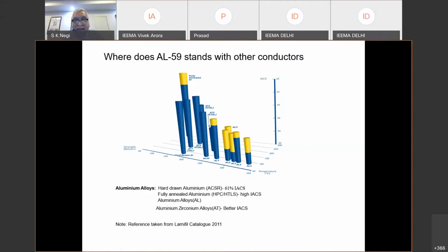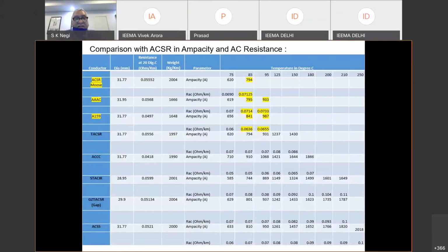So from this we see that AL59 conductor can stand up to 95 degrees centigrade, with a conductivity of 59%, and has a better capability of standing temperature as well as lesser sag than the ACSR Moose conductor. And when I put on chart this ACSR Moose conductor versus AL59, here you can see that ACSR Hormuz at 85 degrees centigrade is carrying 794 amps, but this amps actually is limited, as I said in the beginning, by surge impedance loading, particularly for a line which is more than 150 kilometers.